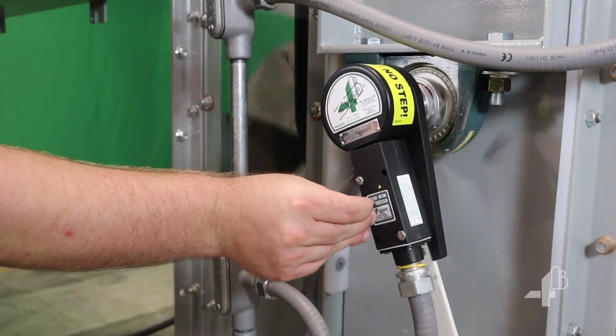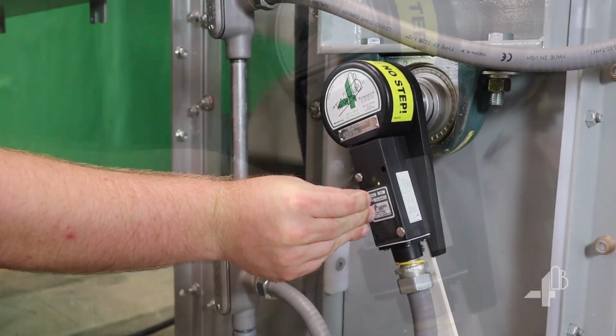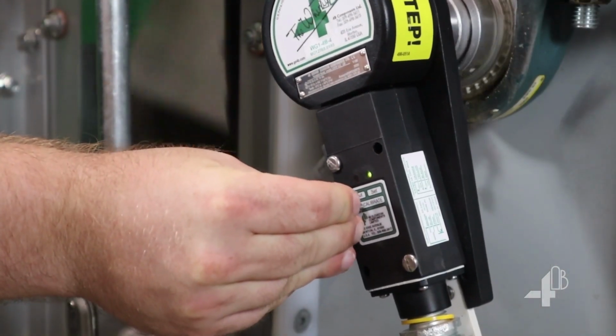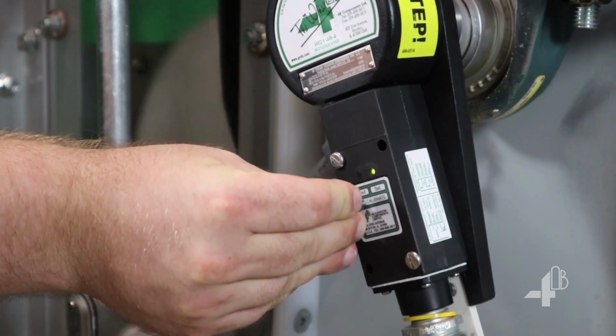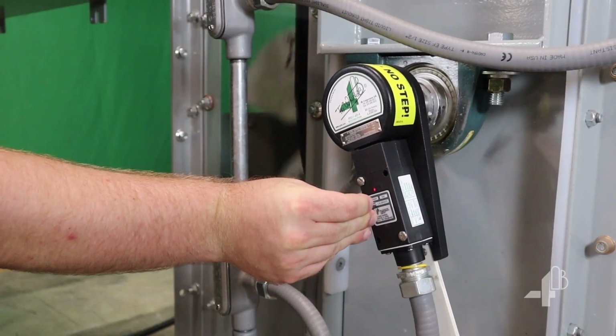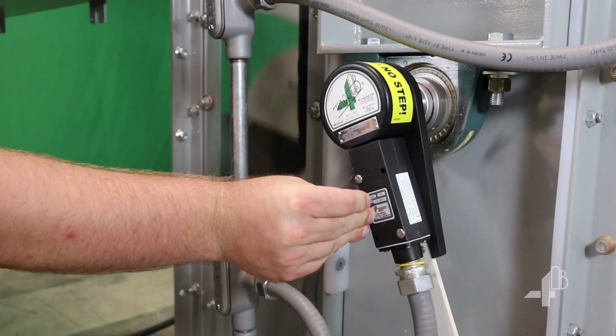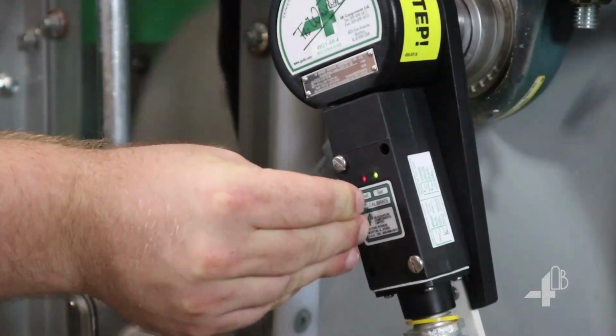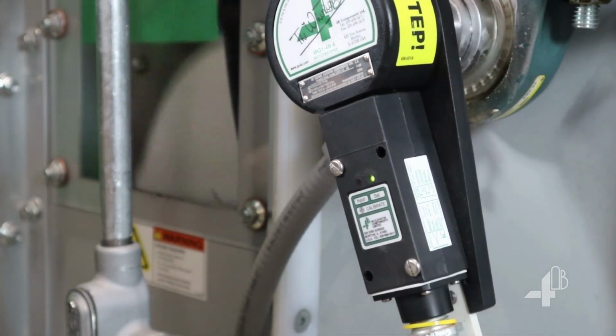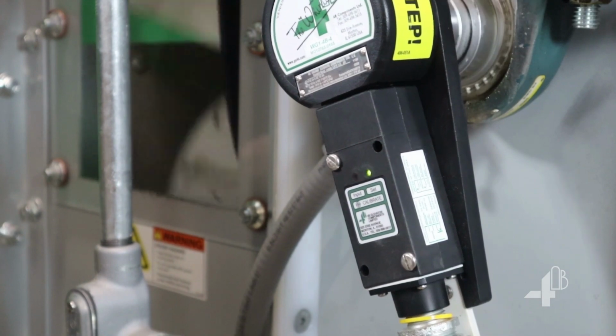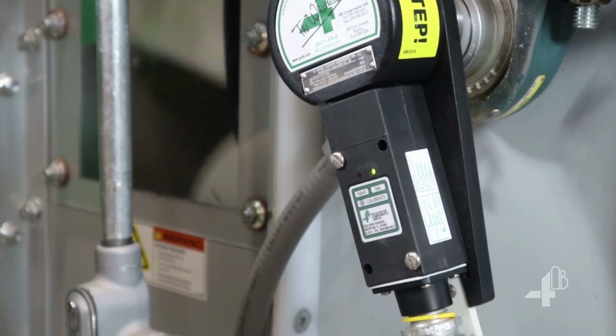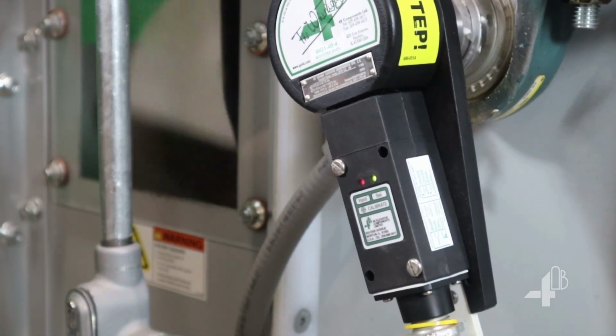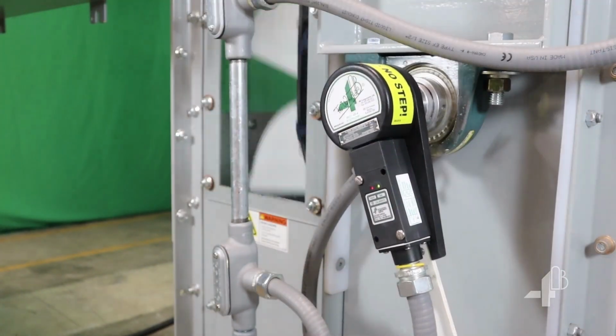Now, place the magnet on the calibration area. See that the set LED flashes green once per second. Hold the magnet in place for the amount of time it takes for the machine to ramp up to full speed, then remove. The set LED should then flash back the same number of times and then stay steady. The unit is now calibrated.